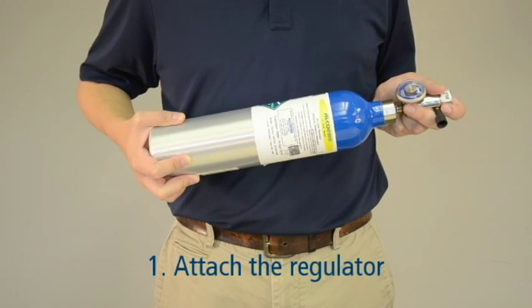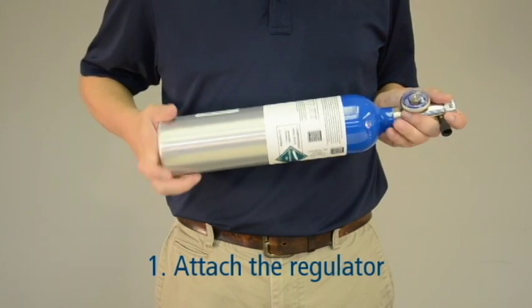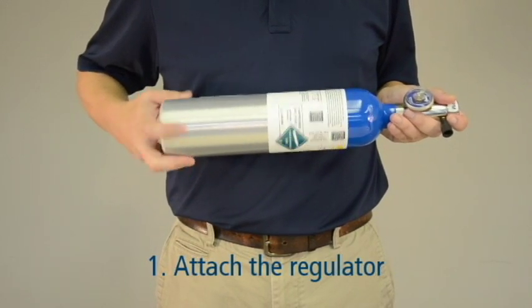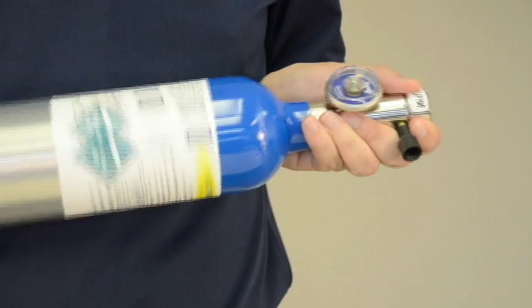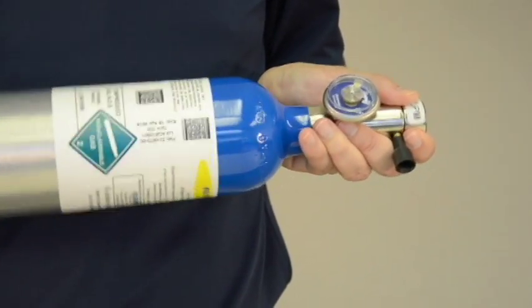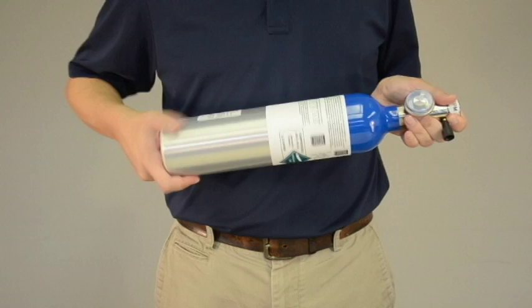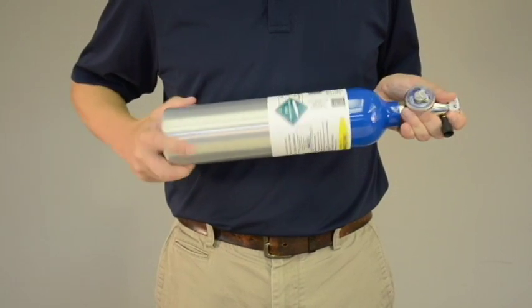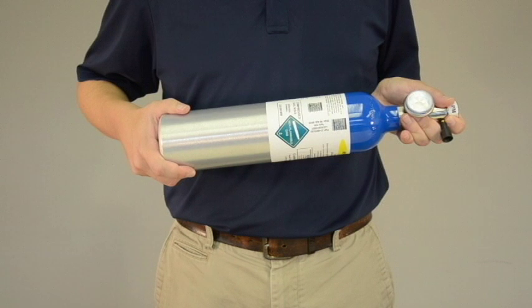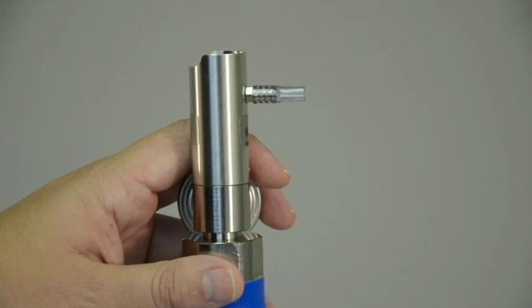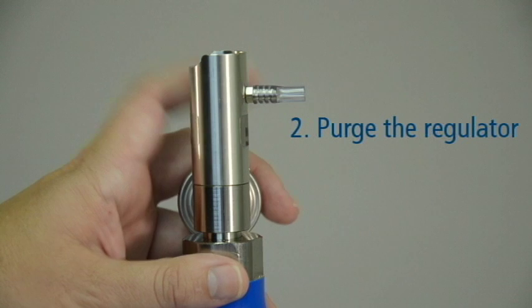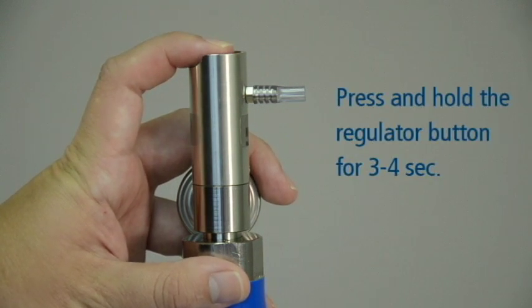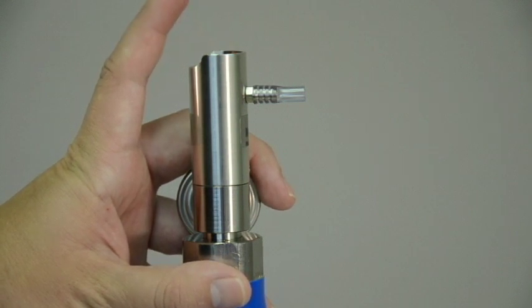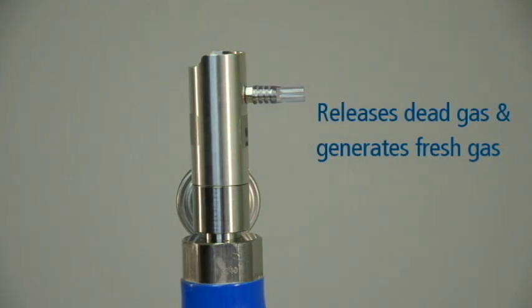First, attach the regulator to the dry gas tank. For safety purposes, point the regulator end of the canister away from your body and away from others. Twist the regulator securely in place, making sure you don't over-tighten. You may hear a pop or a hiss sound as you tighten the regulator. This is normal. Before performing the calibration, it is important to purge the regulator. This is done by pressing and holding the button or valve on the regulator for 3 to 4 seconds. Purging the regulator releases any dead gas that may be present in the regulator and generates fresh gas for the purpose of the calibration.